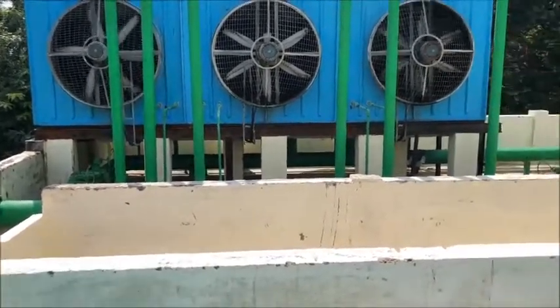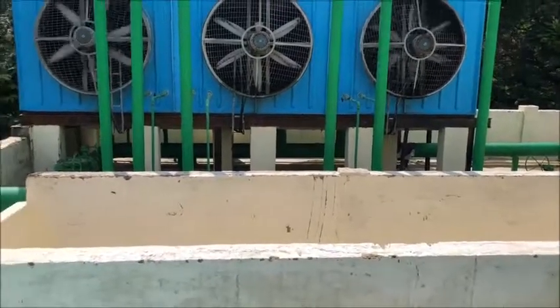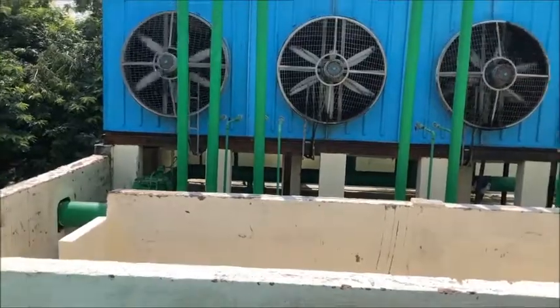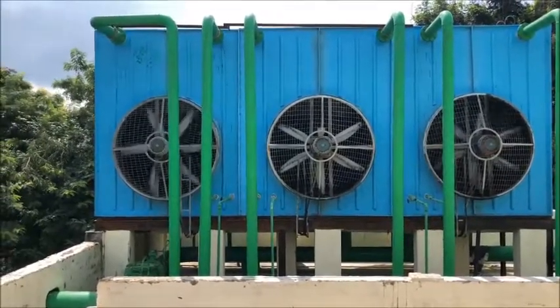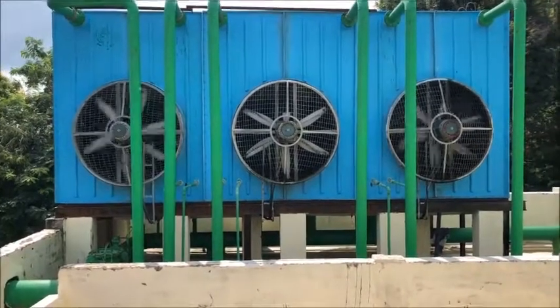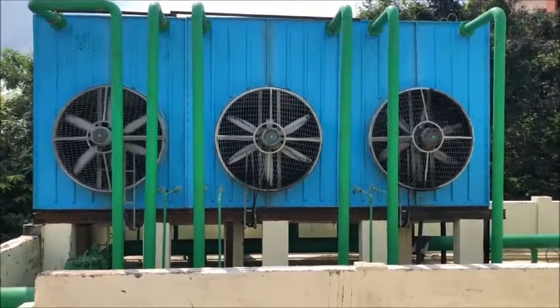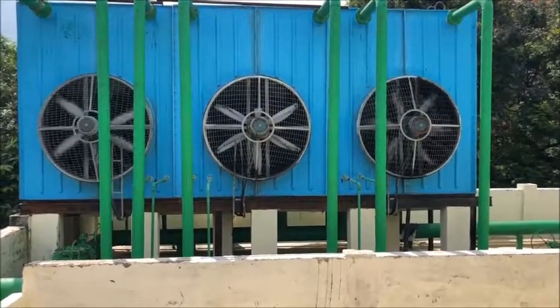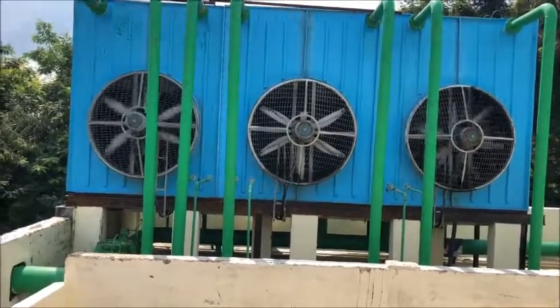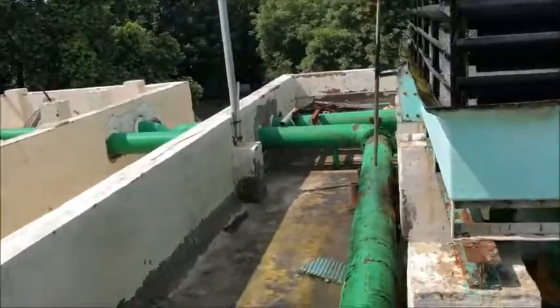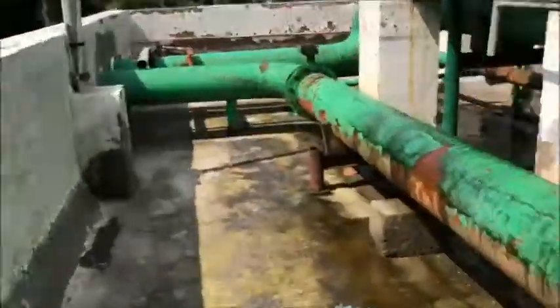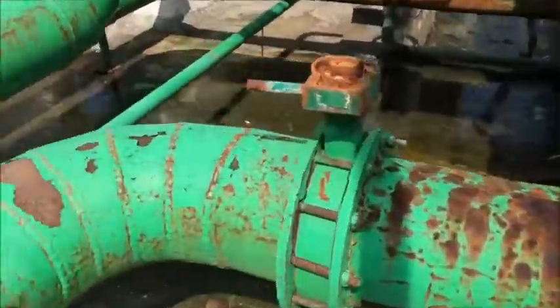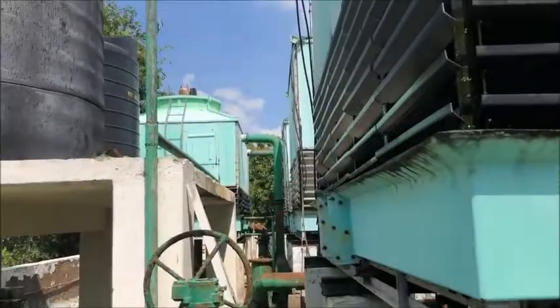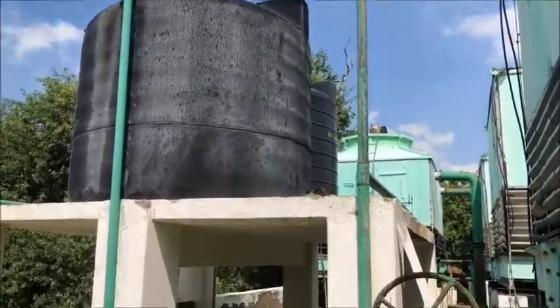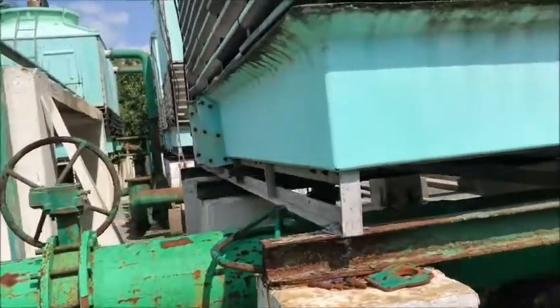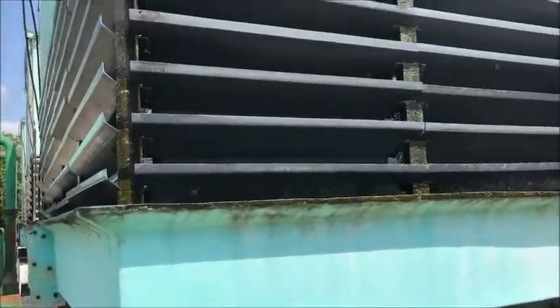In a water cooled system, the refrigerant gas is normally condensed in a shell and tube condenser. Water is used to cool and condense the refrigerant gas and in turn change it into high pressure refrigerant liquid. In this process, the water gets heated and has to be recooled to continue the refrigeration cycle. The cooling of this condenser water is carried out in one of the cooling towers as described above. The extent to which this water can be cooled depends on the ambient wet bulb temperature. The condensing temperature of the refrigerant gas in turn depends on the temperature to which the water is cooled in the cooling tower. That's why the cooling tower selection is very important, and cooling towers are the most efficient water cooling devices. Their approaches have to be kept as low as possible.